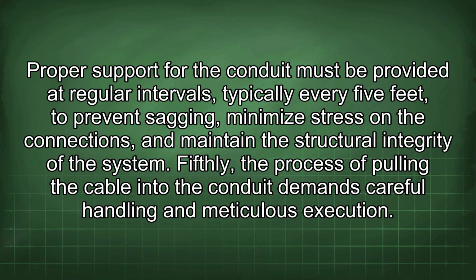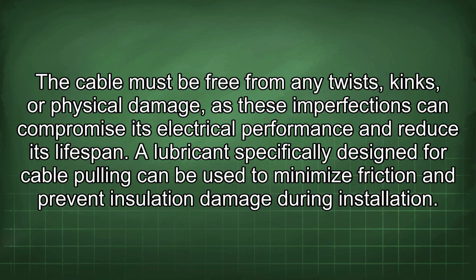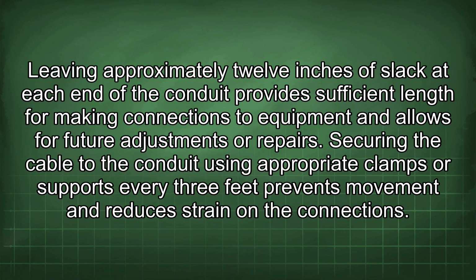Fifthly, the process of pulling the cable into the conduit demands careful handling and meticulous execution. The cable must be free from any twists, kinks, or physical damage, as these imperfections can compromise its electrical performance and reduce its lifespan. A lubricant specifically designed for cable pulling can be used to minimize friction and prevent insulation damage during installation. Leaving approximately 12 inches of slack at each end of the conduit provides sufficient length for making connections to equipment and allows for future adjustments or repairs.